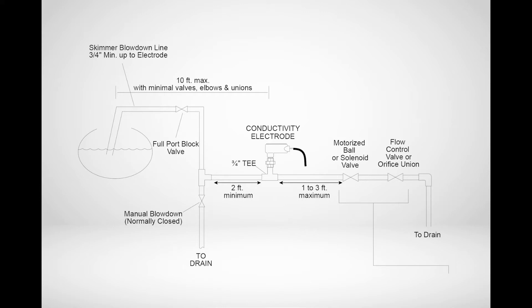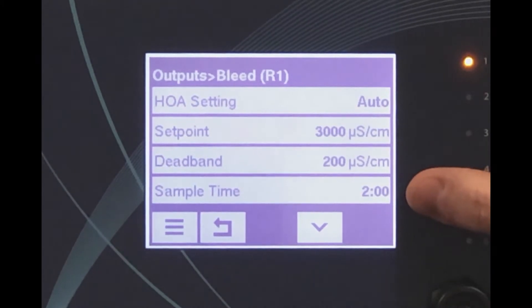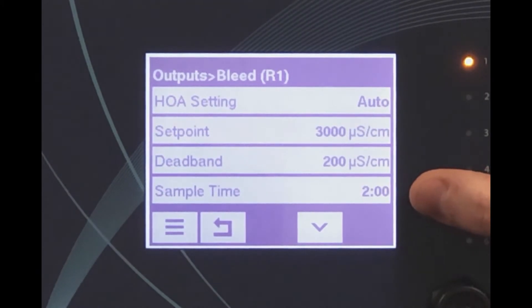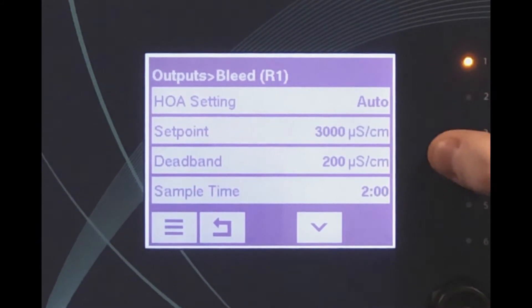The majority of boilers treated are smaller and cannot handle a continuous blowdown for continuous conductivity measurement. Intermittent sampling of the boiler is then the preferred method. In this case, the sensor is plumbed in the actual blowdown line. The simplest form of intermittent sampling will open the blowdown valve for a set amount of time and leave the blowdown valve open as long as the boiler conductivity is over set point minus the dead band.